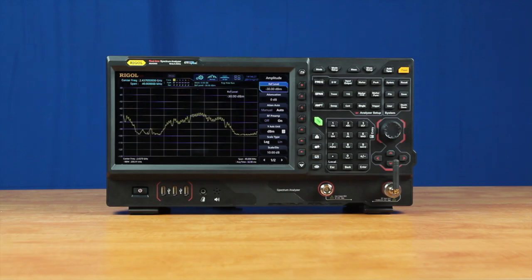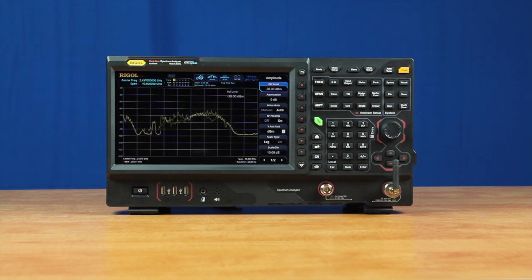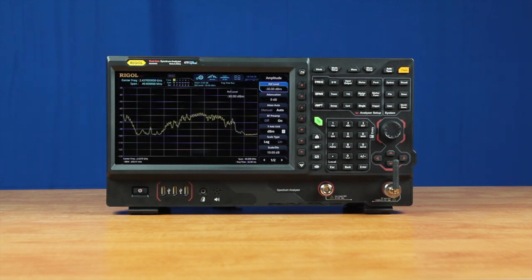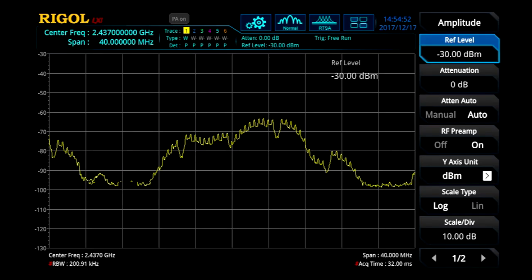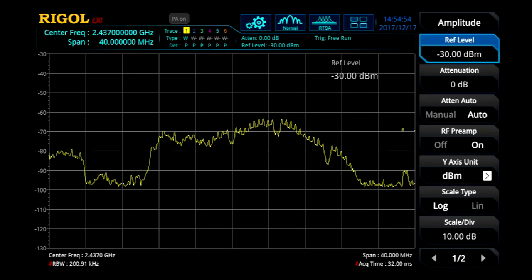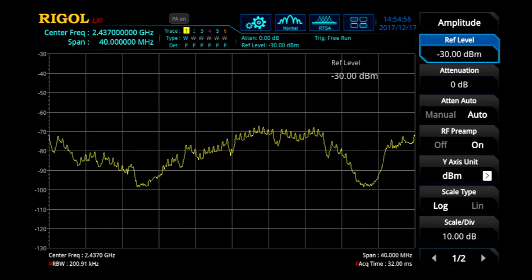We can also set the instrument into real-time spectrum analysis mode for real-time sampling, which gives us the ability to see much more complex and intermittent signals due to the real-time bandwidth and very high POI. With up to 40 MHz of real-time bandwidth and the ability to capture a pulse as short as 7.5 microseconds, we're able to capture most intermittent and complex signals. Here we can actually see on the screen the Wi-Fi channel nearby, just captured by the antenna.